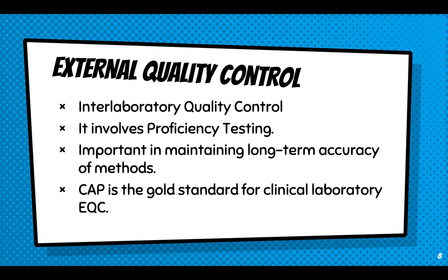So what we're trying to do here is actually to perform your tests. You're going to run your external QC material in the very same manner as you do your internal QC and how you process your patient specimen. So what we're trying to assess here, of course, again, are the three main objectives of your quality control: to check the stability of your machine, to check the quality of your reagent, and also to assess the competence of your technical staff.